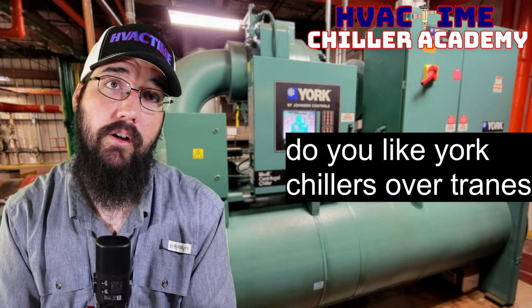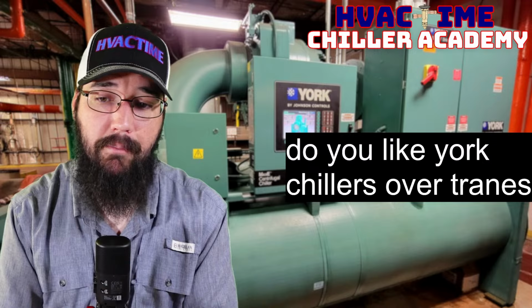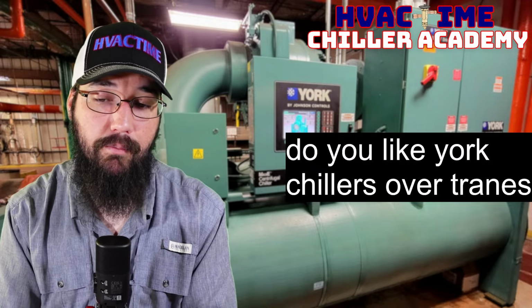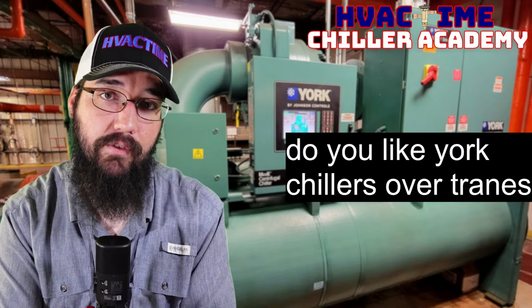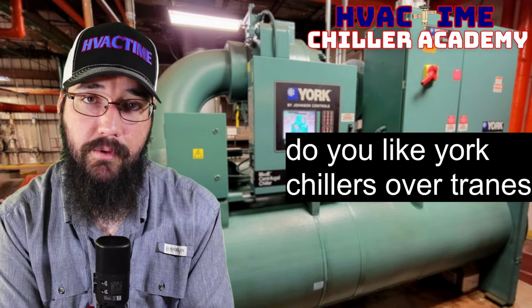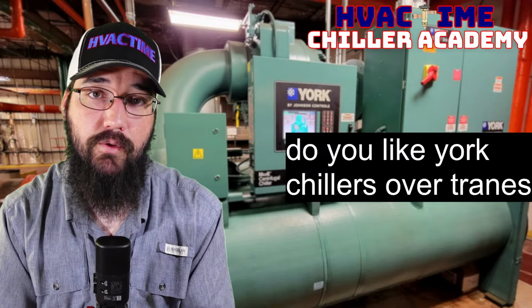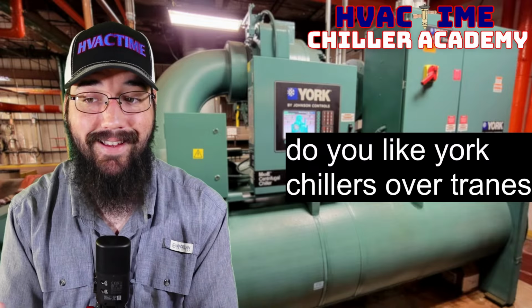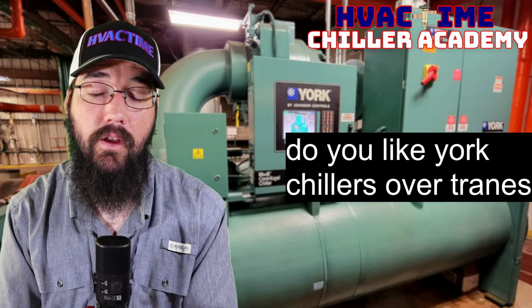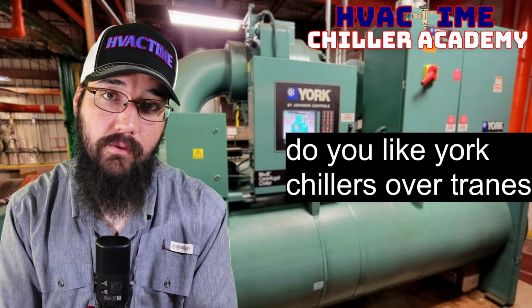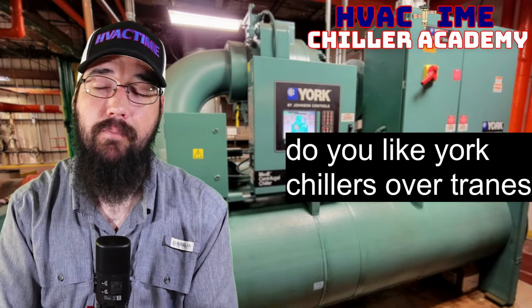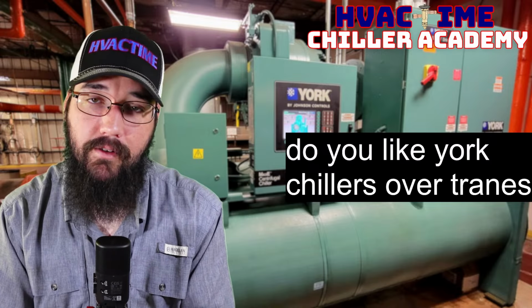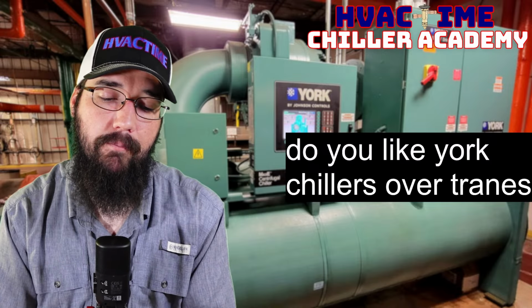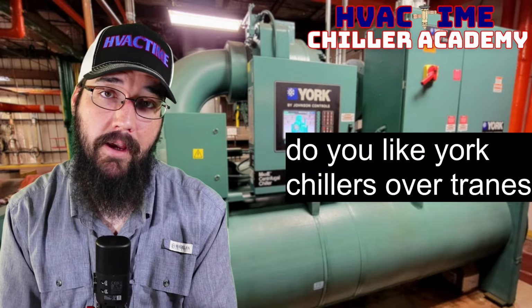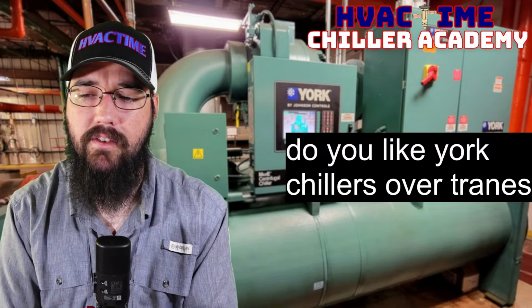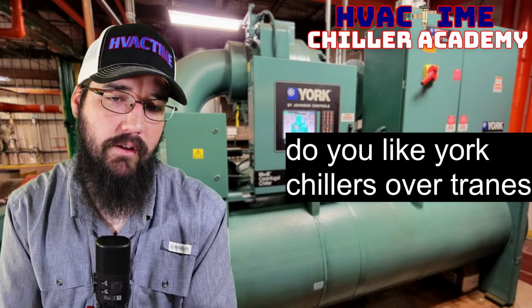So the only way you can get a low pressure with York right now is going mag bearing, but you may not want a mag bearing for your particular site. You may prefer to have an oiled machine. So that comes back to what you need and your reliability. The mag bearings have been having a lot more issues compared to oiled machines, right? That's just a fact. And the mag bearing technology is not perfect. So if you want a low pressure but you don't want mag bearing, you have to go Trane, right? That's the kind of stuff you get into, and outside of that, I really don't care.